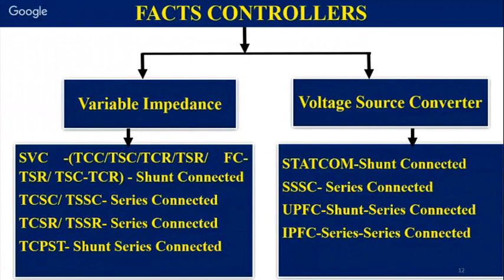In variable impedance, we have SVC, that is static VAR compensators, which are classified depending on the conventional components used. Conventional components like inductance and capacitor banks are used, but they are many times controlled by semiconductor devices. In many places they are even right now installed with mechanical switches, but mechanical switches have their own disadvantages like speed and repeatability, which can be overcome by semiconductor switches. So SVC is one of the variable impedance type FACTS controllers, which is connected in shunt.